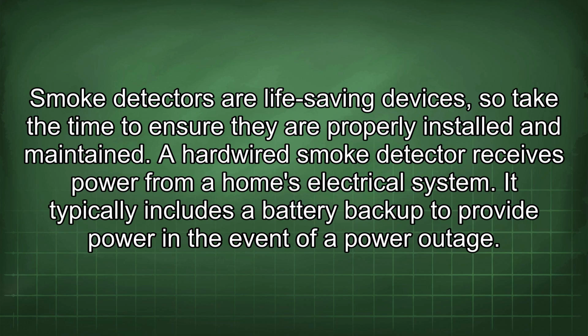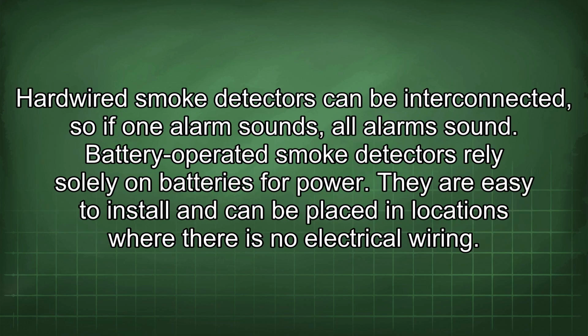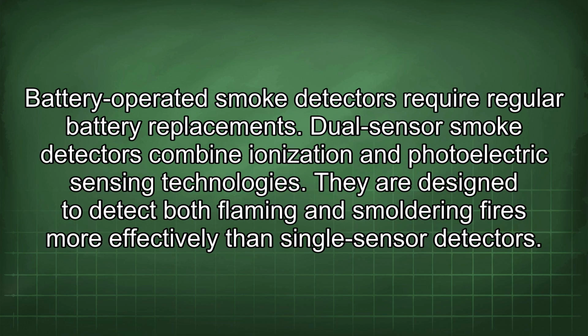A hardwired smoke detector receives power from a home's electrical system. It typically includes a battery backup to provide power in the event of a power outage. Hardwired smoke detectors can be interconnected, so if one alarm sounds, all alarms sound. Battery-operated smoke detectors rely solely on batteries for power. They are easy to install and can be placed in locations where there is no electrical wiring. Battery-operated smoke detectors require regular battery replacements.